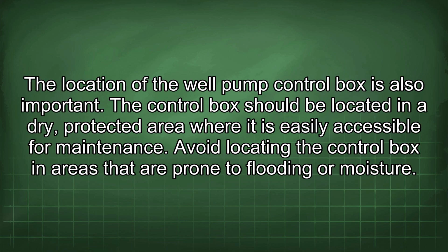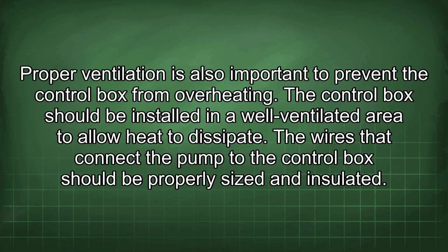The location of the well pump control box is also important. The control box should be located in a dry, protected area where it is easily accessible for maintenance. Avoid locating the control box in areas that are prone to flooding or moisture. Proper ventilation is also important to prevent the control box from overheating. The control box should be installed in a well-ventilated area to allow heat to dissipate.